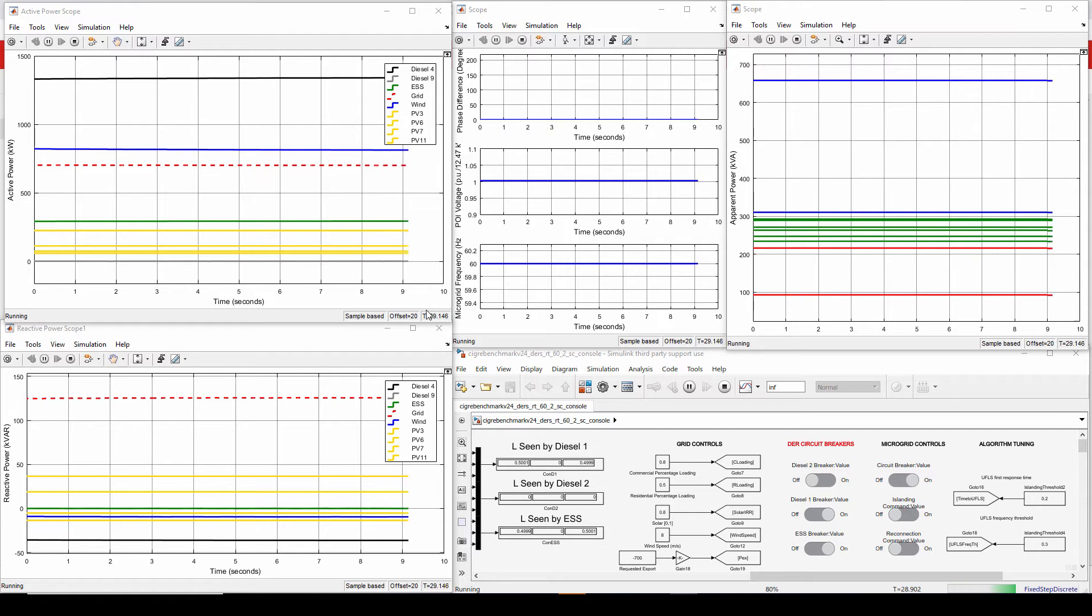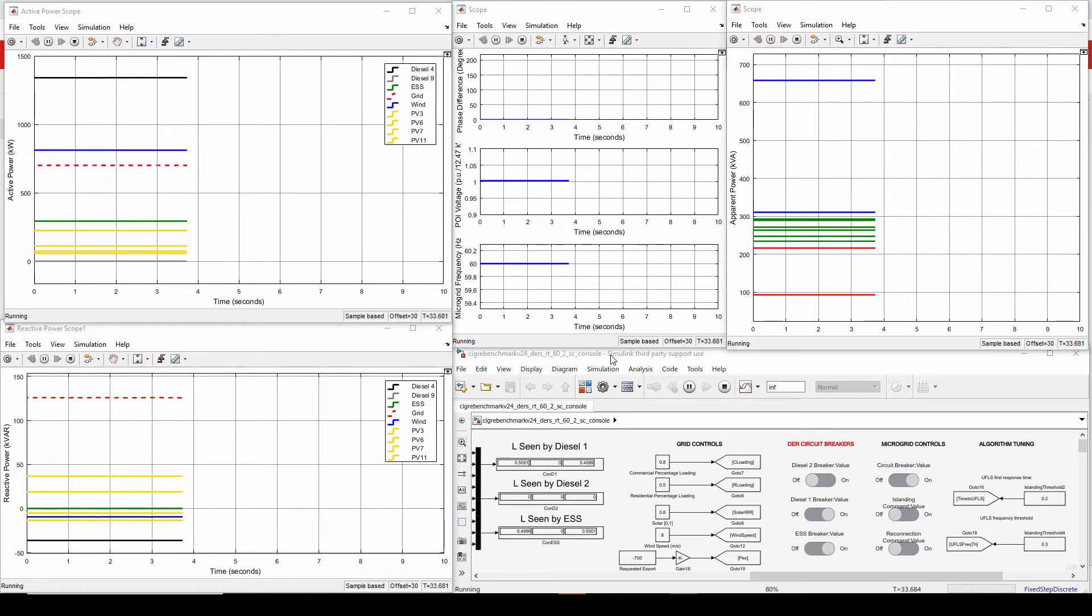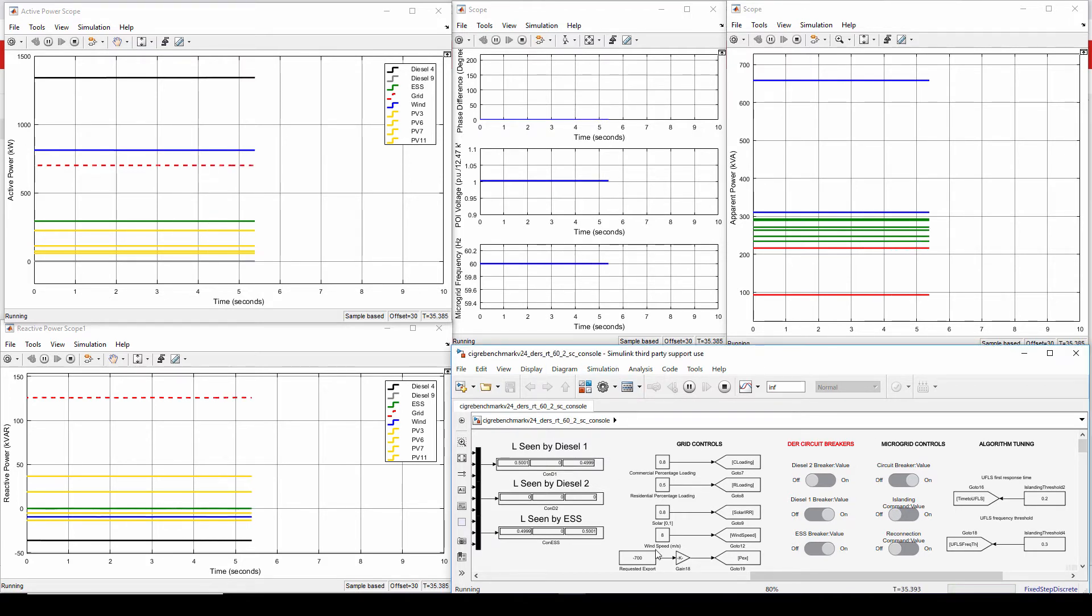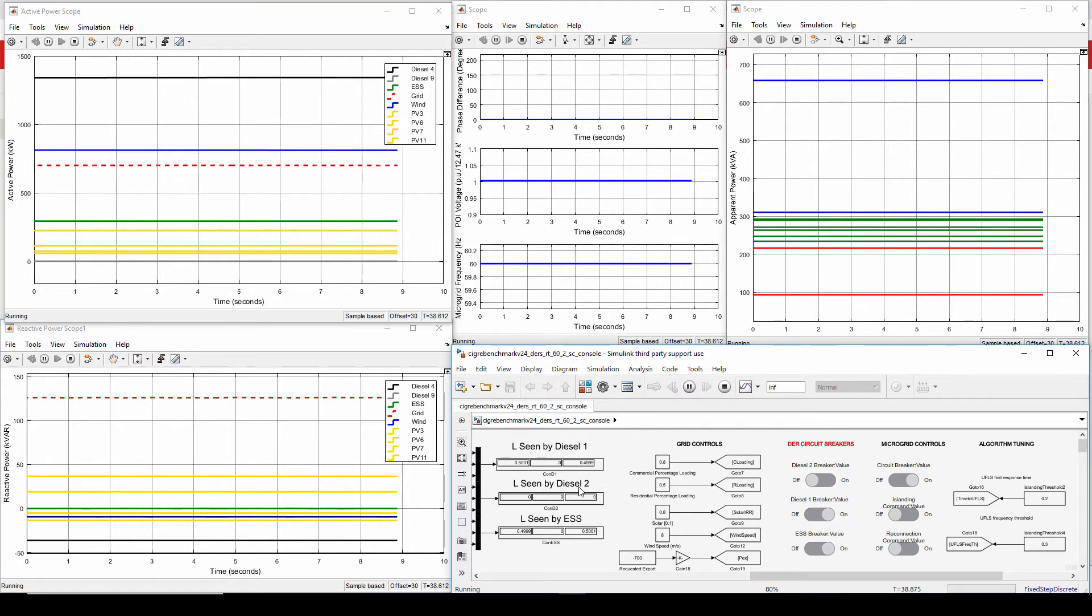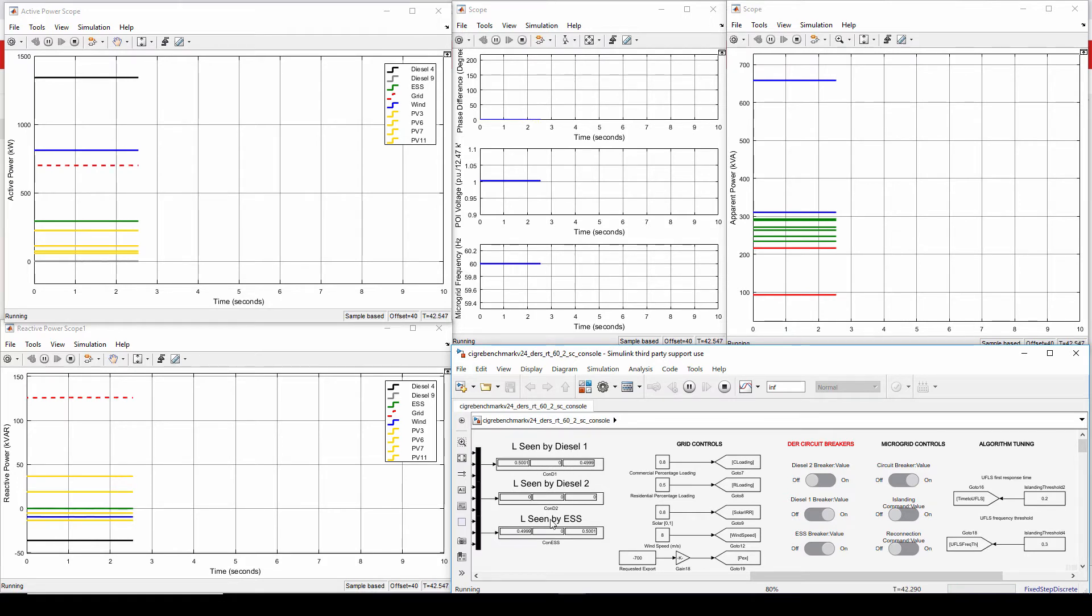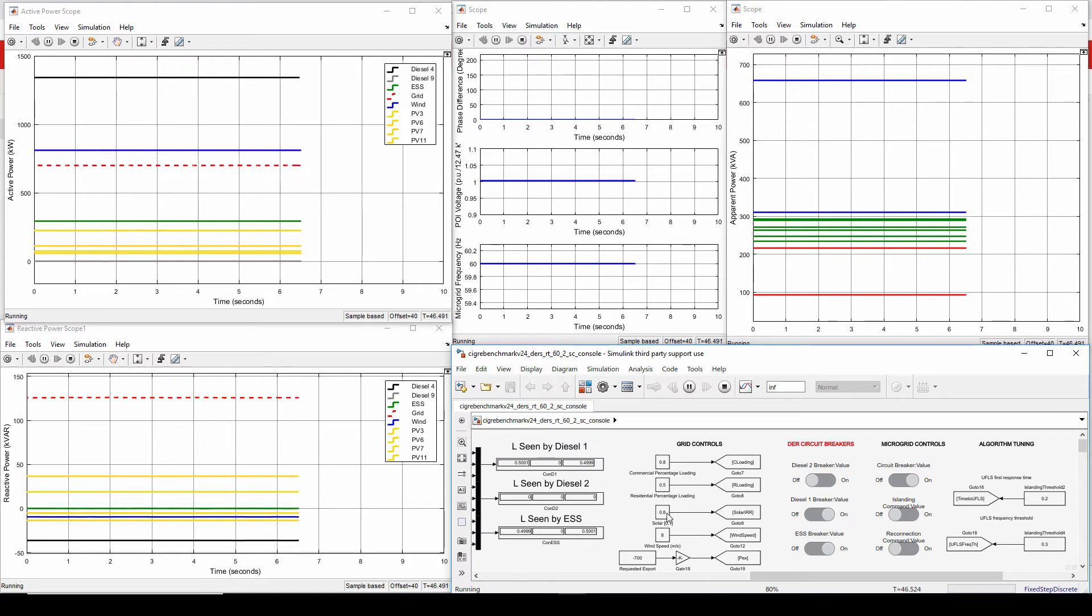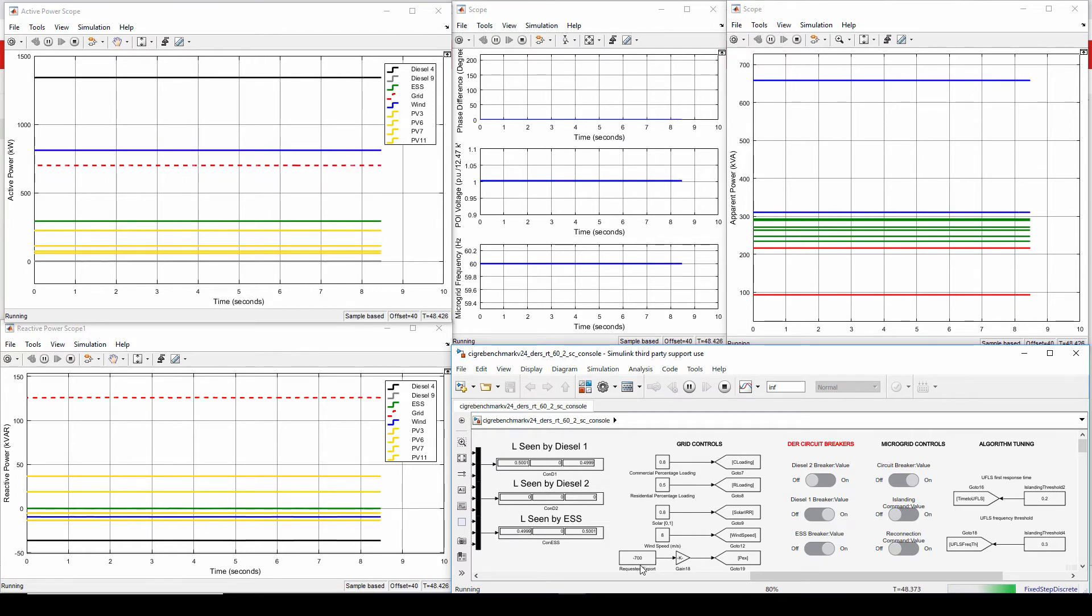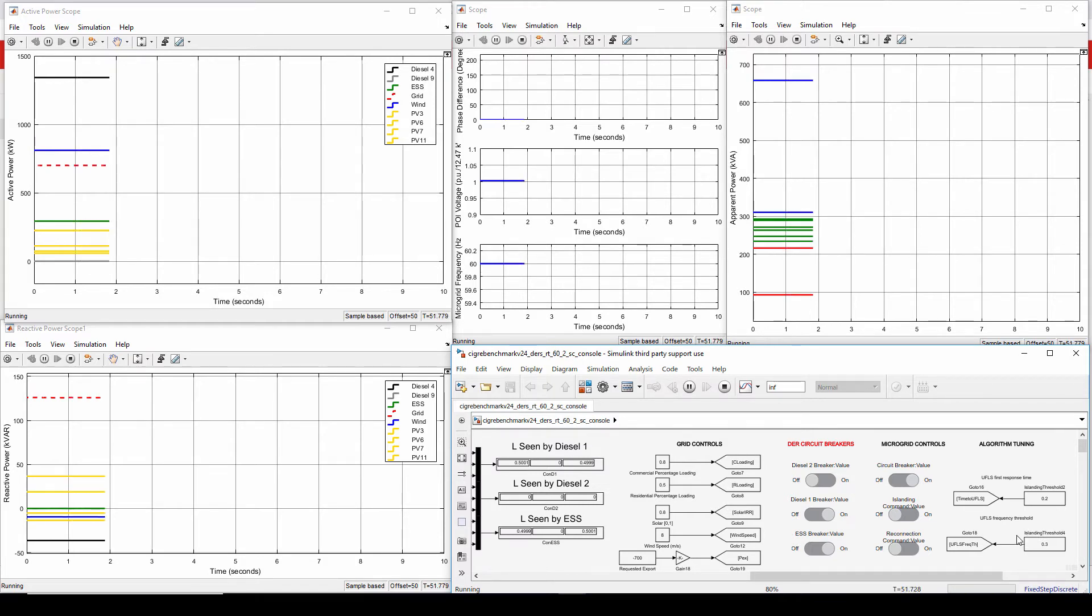So now we switch to the demo of the distributed control system. And before I start presenting the scenarios, let me first give an overview of the console running. So you have a console as one of the subsystems in the real-time simulation. And through this console, you can control many parameters in the microgrid. And you can use it to observe things. For example, I'm getting these L matrices from the Raspberry Pis in the real-time simulation. This presents that diesel 1 is connected to ESS, diesel 2 is disconnected. And I have some grid controls here. I can control the commercial and residential loading, how much solar output there is by emulating the solar radiation, and how much wind speed there is, and how much the required power exports at the point of interconnection. I also have algorithm tuning, which we're going to play with a little bit later in the demo, and some microgrid controls.